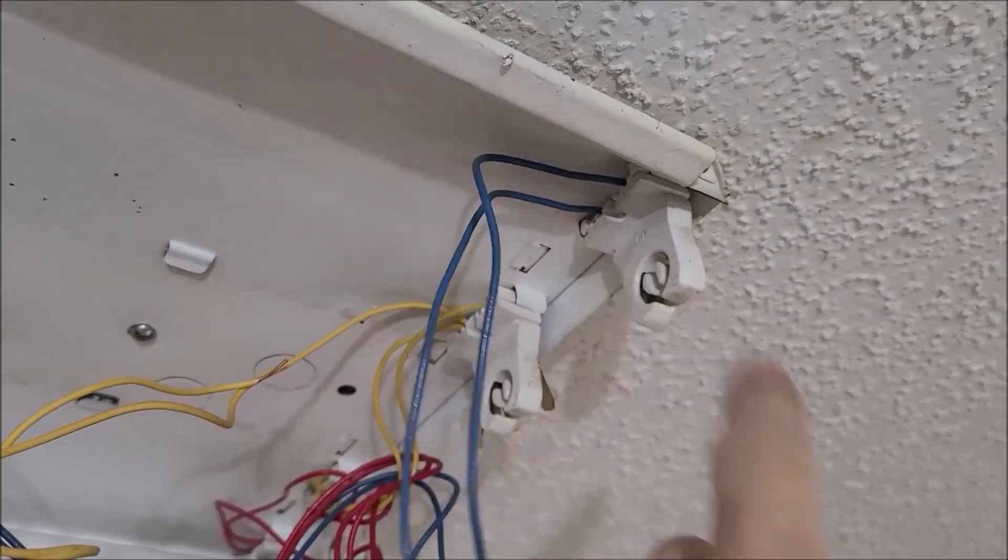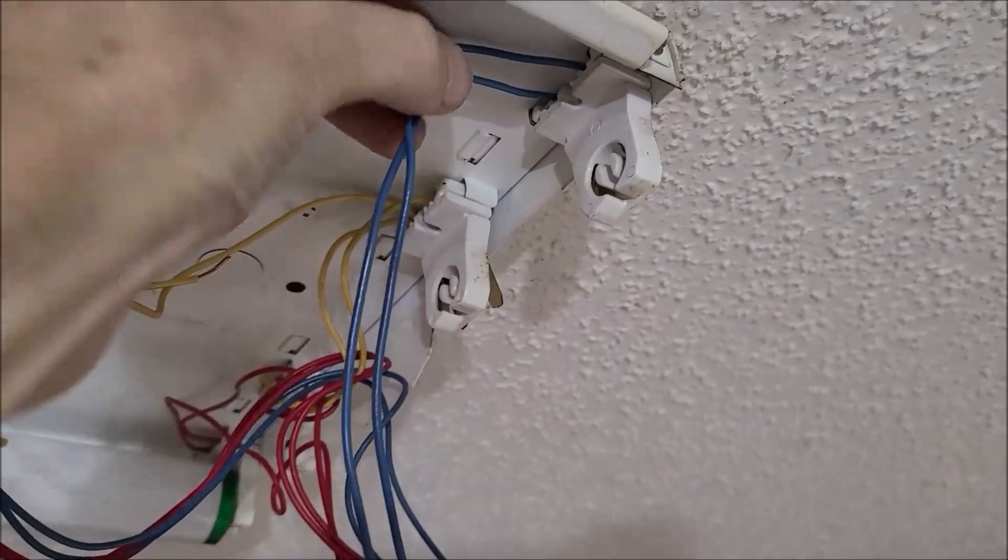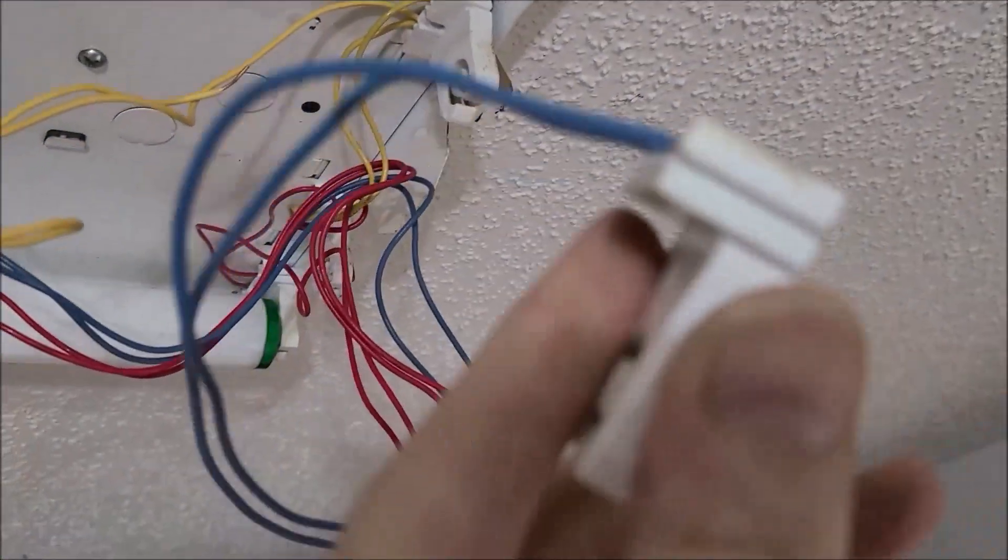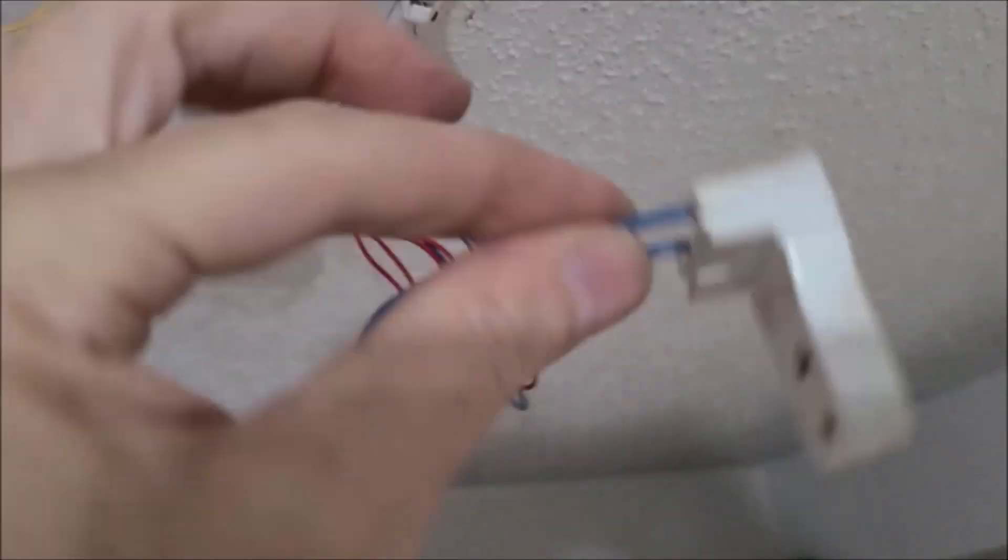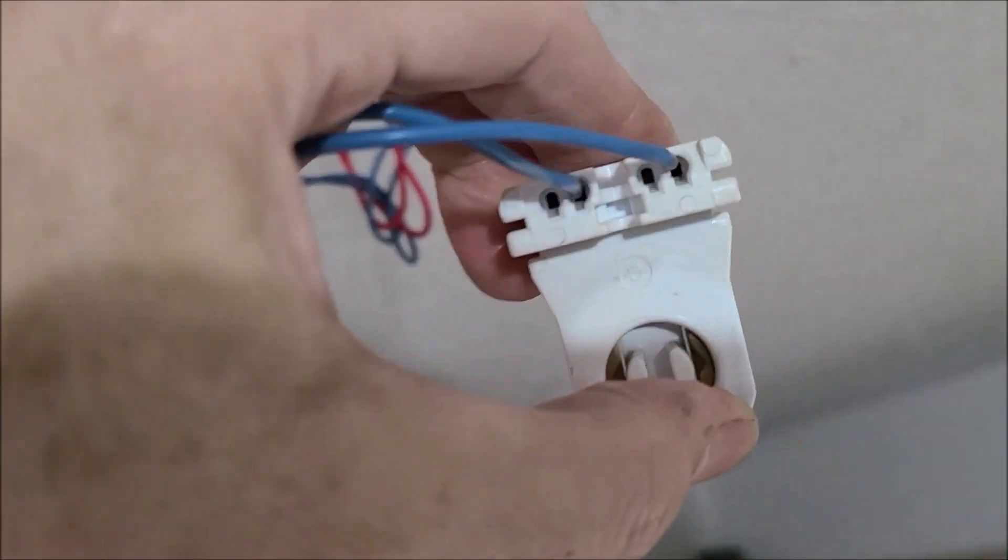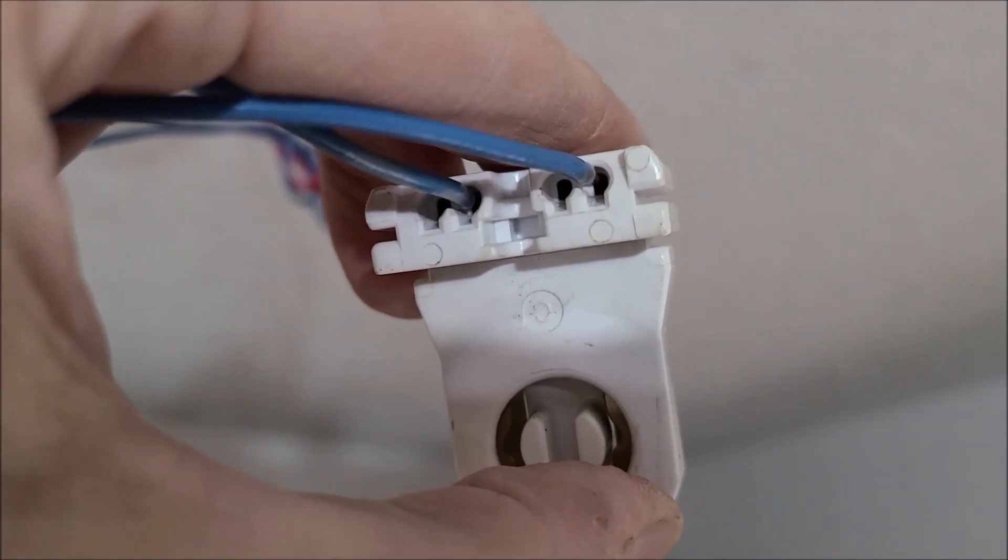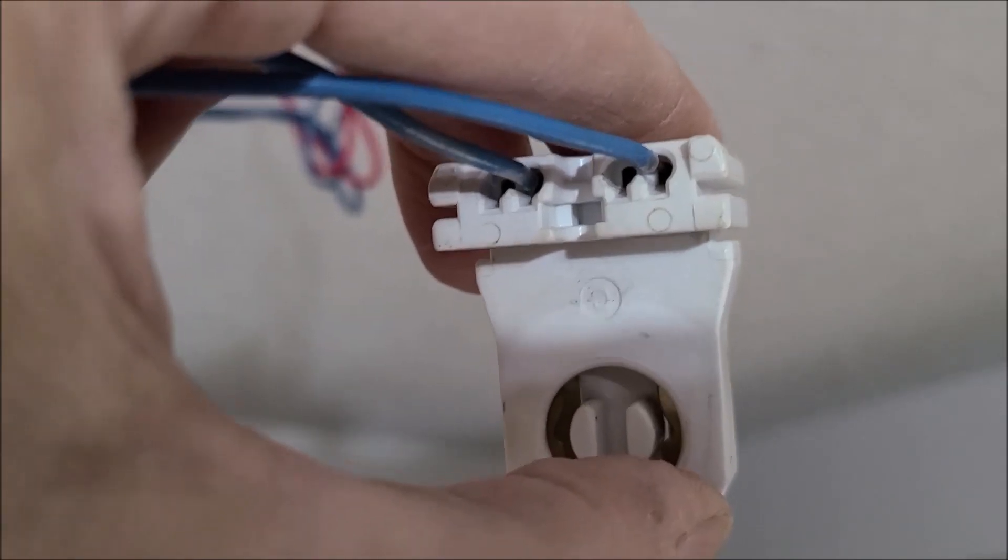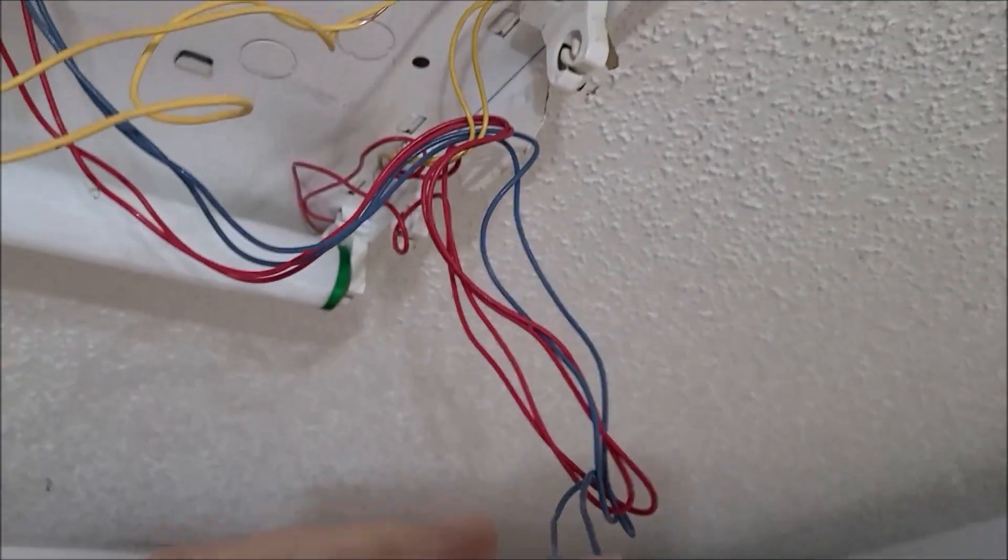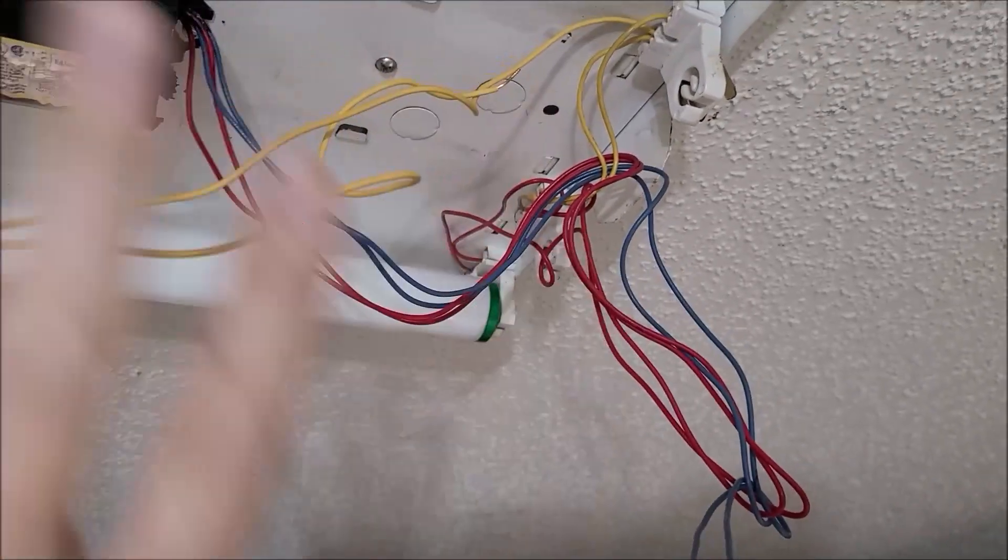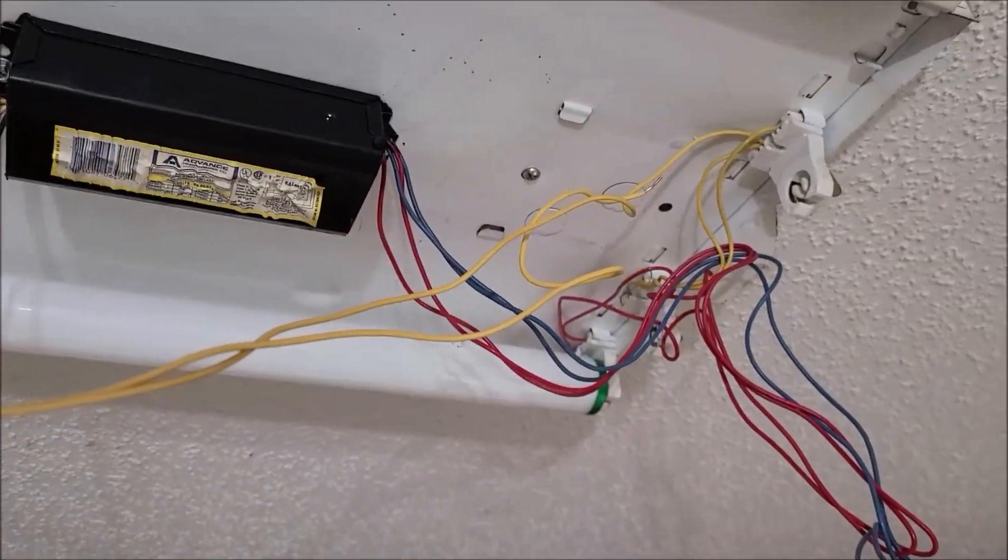The next thing we got to do is just eliminate all the wires, all ballast. First thing is getting the wires out of these sockets. Of course, only got one hand, but the idea is hold this in one hand, at the same time pull and wiggle this wire. Let me see, I'm not going to do it. If you just hold this in one hand, at the same time add pressure and just wiggle it back and forth and it'll pop right out. If you have a real sharp little tool, you're reaching that little hole and you can press down a little hole in the six o'clock position. You have like one little sharp, scratchin', dental tools, and that'll release it. So my next thing is right now I'm going to go pull all these wires out and then stick the sockets back in place so all the wires will be gone, pulled out, and I'm going to remove the ballast and then we'll start wiring up the new ballast. Shouldn't be no problem.